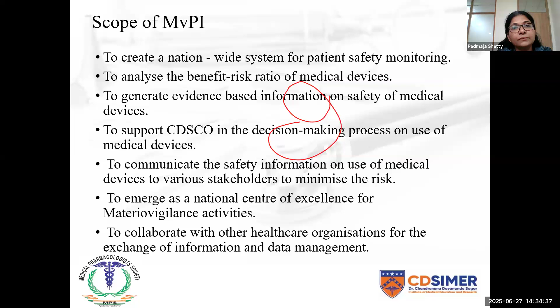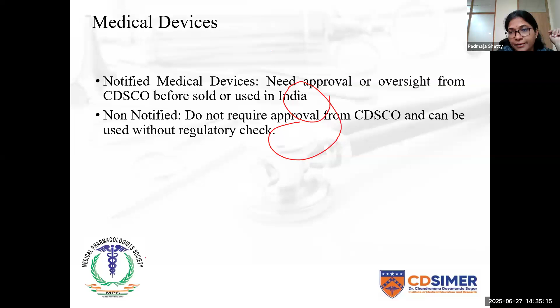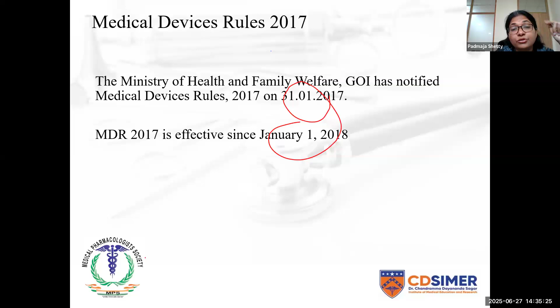So medical devices: CDSCO has brought about certain criteria for medical device manufacture and its release into the market. That is known as the notified medical devices, which need approval or oversight from the CDSCO before they are sold or used in India. Non-notified devices do not require any approval from the CDSCO and can be used without regulatory check. The Ministry of Health and Family Welfare, Government of India, notified the Medical Device Rules 2017 in 2017, and the Medical Device Rules later came into effect from 2018.